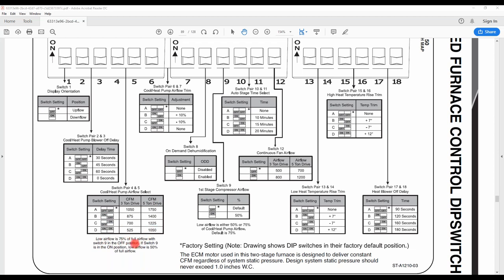Notice they call out switch number 9 at the bottom here. Switch number 9 is if you have a 2-stage air conditioner or 2-stage heat pump. When 9 is in the off position, your first stage airflow will be 75% of the rated airflow you have selected here. So if you have 1,050, 75% of 1,050 is approximately 790 CFM. That'll be your first stage airflow.